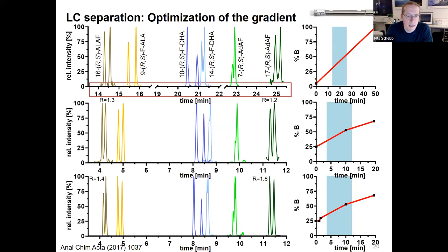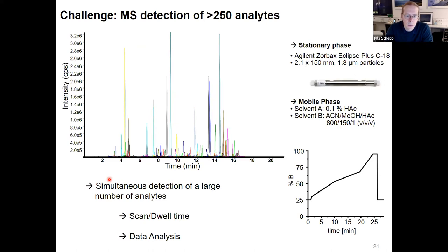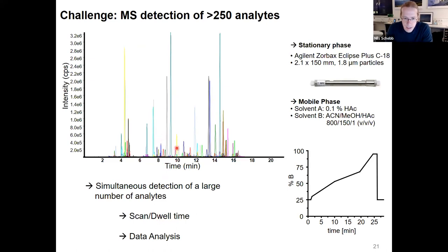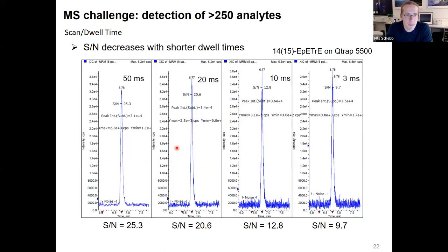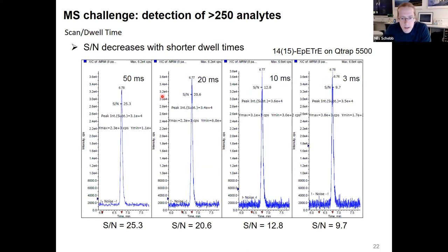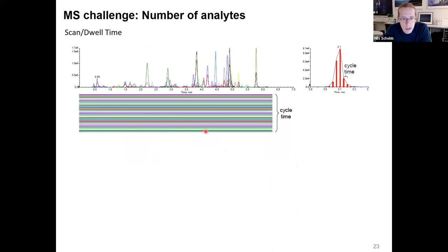If we think about a method covering a lot of different analytes, there are some general challenges for a multi-analyte targeted method — specifically the time the instrument spends detecting each single compound. Even with modern instruments, the longer the dwell time is, the better the signal-to-noise ratio is. If we think about a method covering more than 250 transitions including internal standards, monitoring all these transitions all the time would result in a very long cycle time that would not yield enough data points per peak.